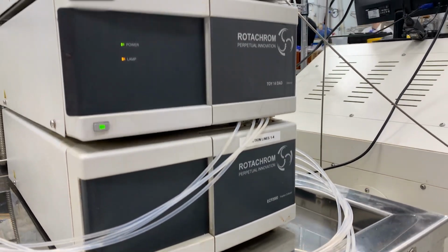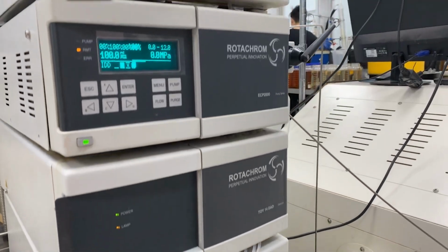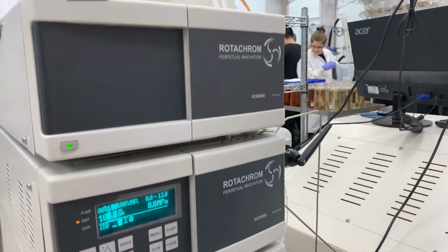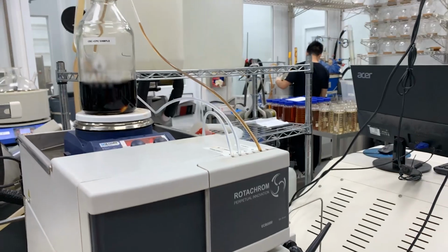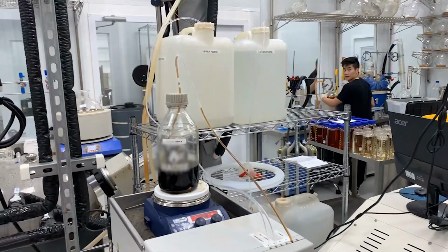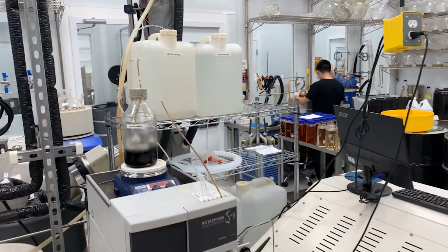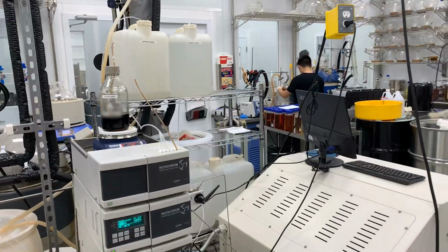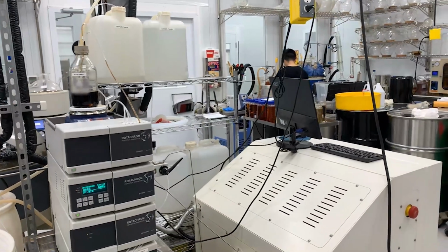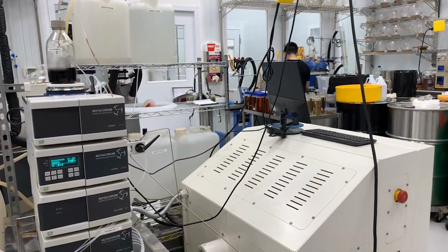Certainly, for lab safety, we need to have the proper safety precautions. What happens if somebody accidentally spills solvent? In that case, we need to have an emergency zone. It's very important that the unit is grounded—there's the green-yellow cable on the side, which has to be on a separate grounding.